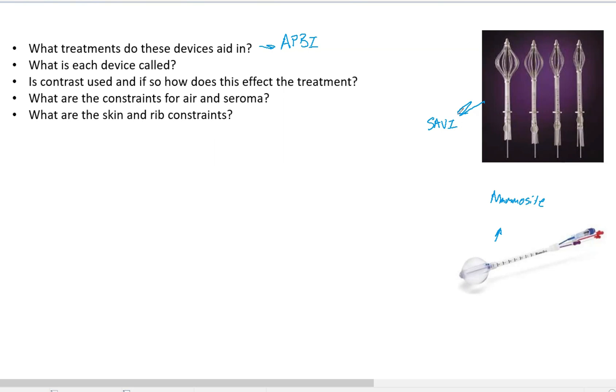We also have the SAVI up here. This is the Strut Adjusted Volume Implant, that is what SAVI stands for. Now this can be expanded to different diameters as you see in this picture. Some are kind of skinny and not very big, and other ones get very large and can take up a lot of volume. That allows for the highest degree of optimization. It leads to dose underestimation however because the center is filled with air, so it underestimates dose about three to four percent.